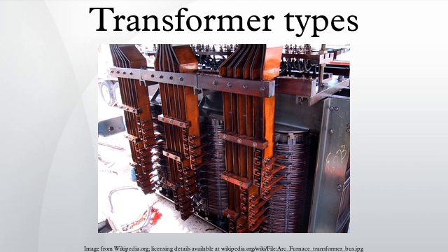Voltage transformers are a parallel connected type of instrument transformer, used for metering and protection in high-voltage circuits or phase shift isolation. They are designed to present negligible load to the supply being measured and to have an accurate voltage ratio to enable accurate metering. A potential transformer may have several secondary windings on the same core as a primary winding, for use in different metering or protection circuits. The primary may be connected phase to ground or phase to phase. The secondary is usually grounded on one terminal.